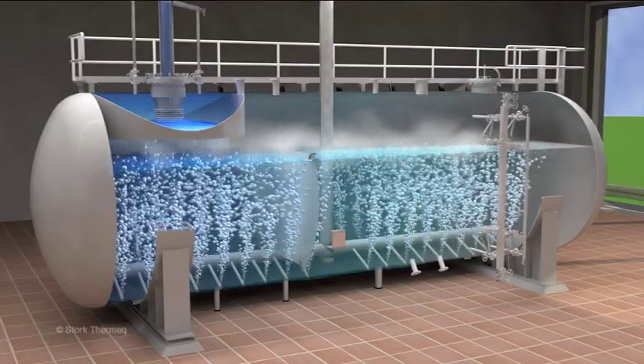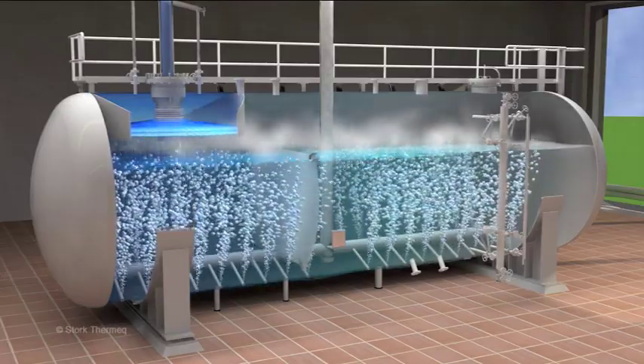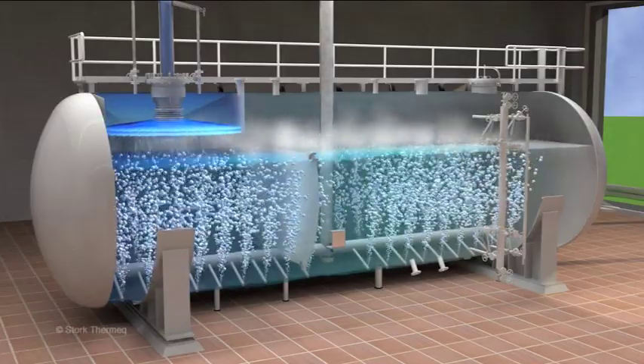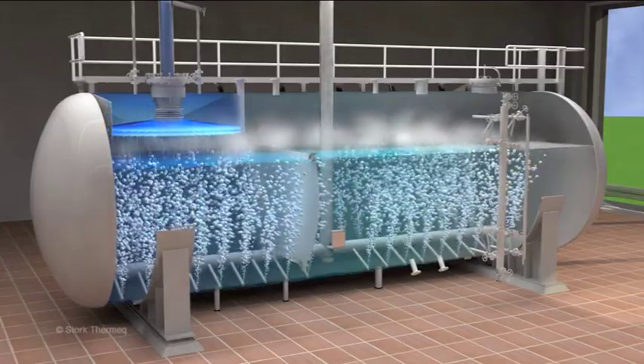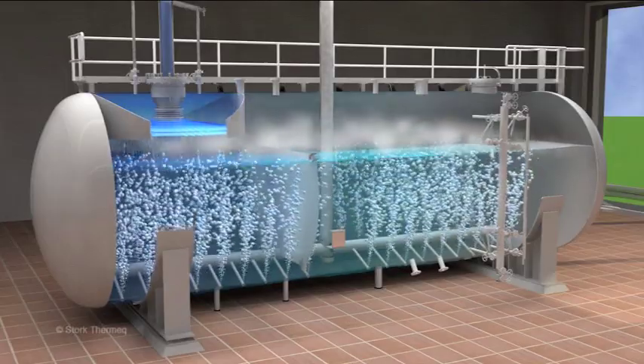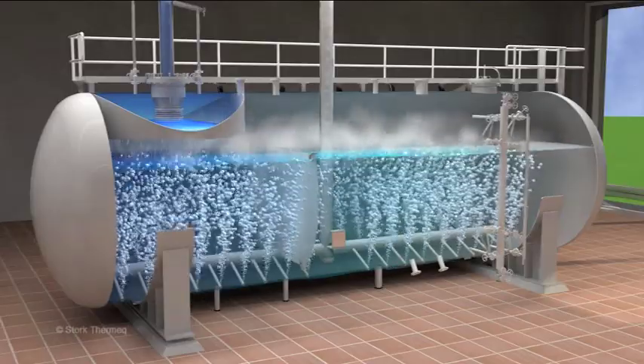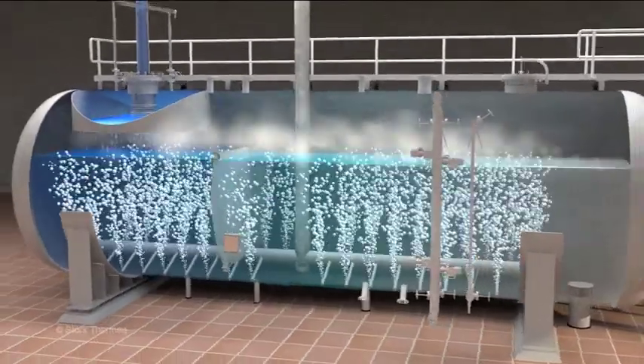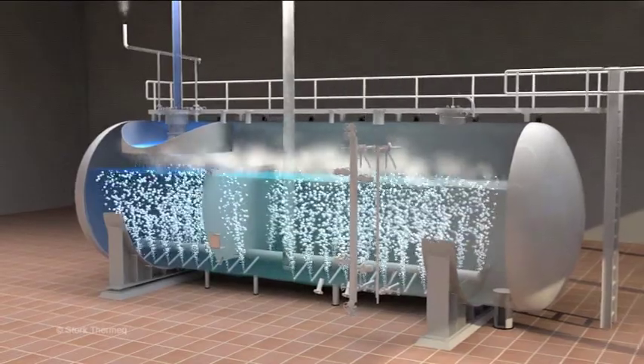The Stork deaerator can achieve a reduction of oxygen concentrations to levels below 7 ppb without oxygen scavengers. The sprayer ensures heating up of condensate to saturation temperature and the pre-deaeration takes place in this area. The Stork deaerator ensures a good contact between water and steam, allowing non-condensibles to move from the water to the steam. Finally, the non-condensibles are vented into the atmosphere with a minimum vent loss.